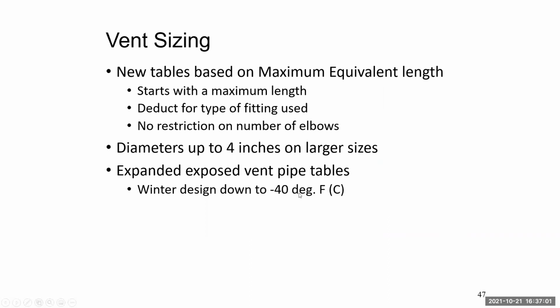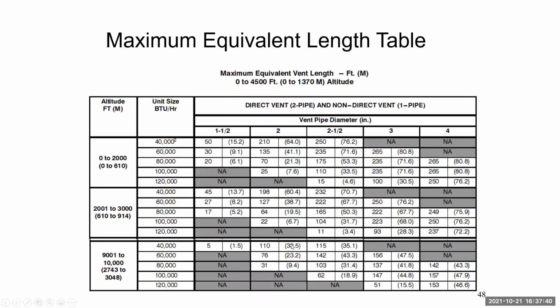So, vent sizing, please pay attention to this in your manuals too. Things have gotten critical with vent sizing. Everything's a 2-inch takeoff, and then you're going to go into 2.5, 3, 4, whatever be the case. But make sure you are following your instructions and checking your piping charts before you start piping, because nothing will upset you more than the gas company coming out and nailing you, or you start getting pressure switch problems because your vents are wrong. So this is just a brief overlay of the sizing charts.